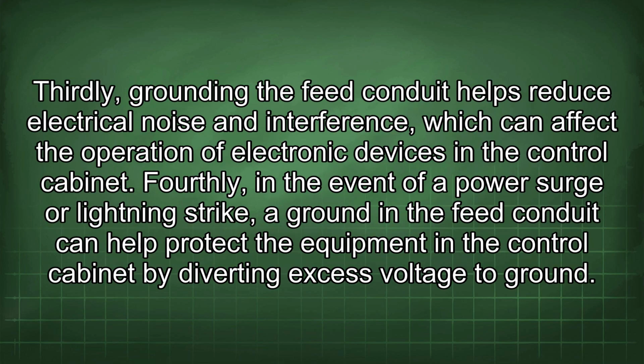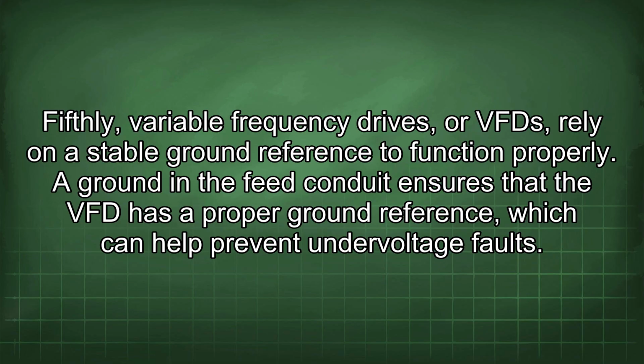Thirdly, grounding the feed conduit helps reduce electrical noise and interference, which can affect the operation of electronic devices in the control cabinet. Fourthly, in the event of a power surge or lightning strike, a ground in the feed conduit can help protect the equipment in the control cabinet by diverting excess voltage to ground. Fifthly, variable frequency drives, or VFDs, rely on a stable ground reference to function properly.